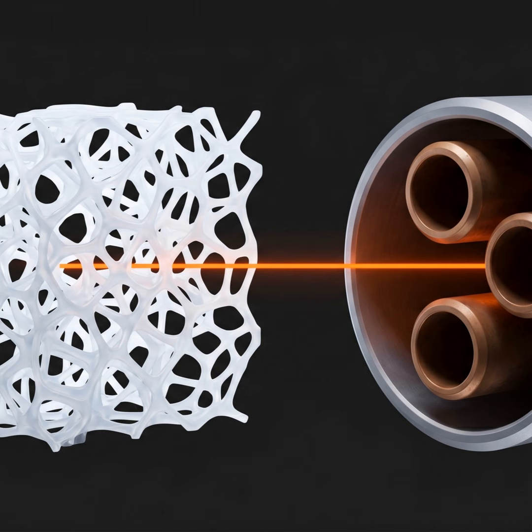One of the experts on the forum points out that if Don tries to use a standard, bare, smooth copper tube to dissipate the compressor's heat into the ambient air, that tube would have to be hundreds of feet long. The math proves that a simple, smooth pipe cannot shed the thermal burden. The boundary layer of the air just resists the heat transfer. Which is why real industrial condensers require massive heat sink arrays. Yes, they have to attach hundreds, sometimes thousands of thin aluminum fins to the copper piping to artificially expand the surface area just to force that heat out into the atmosphere.